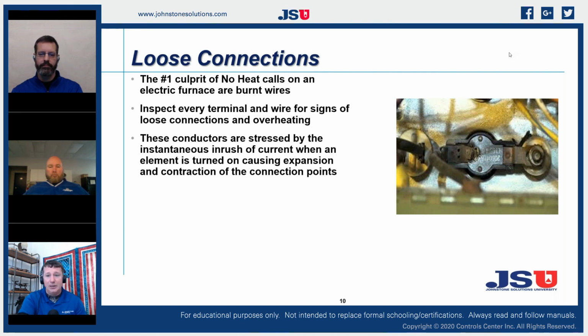And we're going to see it a lot in our temperature limits and in our overloads and in our crimp connections. So even the terminals that we use on our wires have a specific temperature range. And I'll tell you, the one thing that I find in the industry is that our crimp terminals, our wire terminal ends, don't have the same temperature ratings. And it's important that we know what those ratings are, because most of the wires that we use are 90 degrees C. If I go to the auto parts store and I get some end connectors, they may not be 90 degrees C rating. They're probably going to be 60 degrees C ratings.